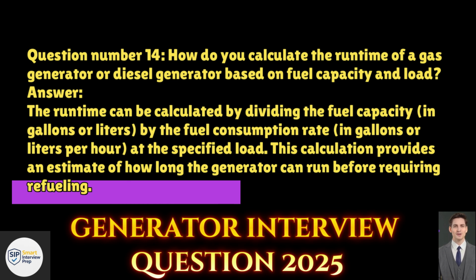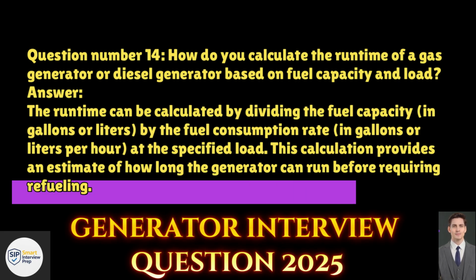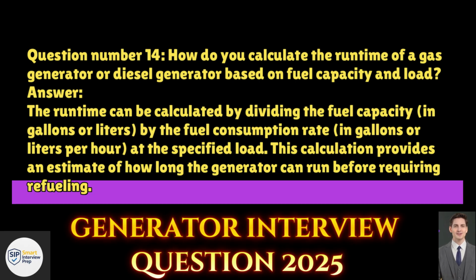The runtime can be calculated by dividing the fuel capacity, in gallons or liters, by the fuel consumption rate, in gallons or liters per hour, at the specified load. This calculation provides an estimate of how long the generator can run before requiring refueling.